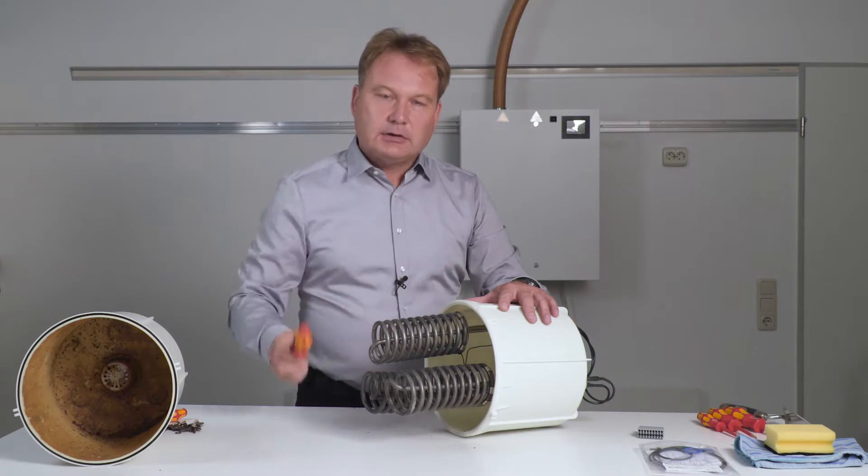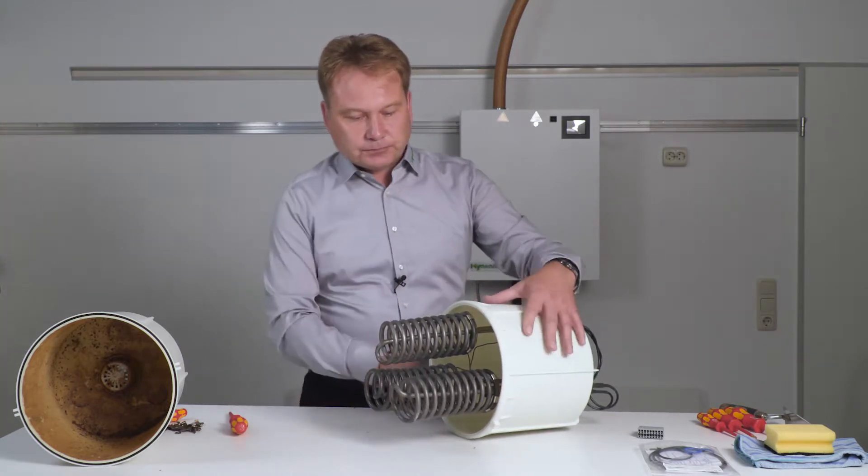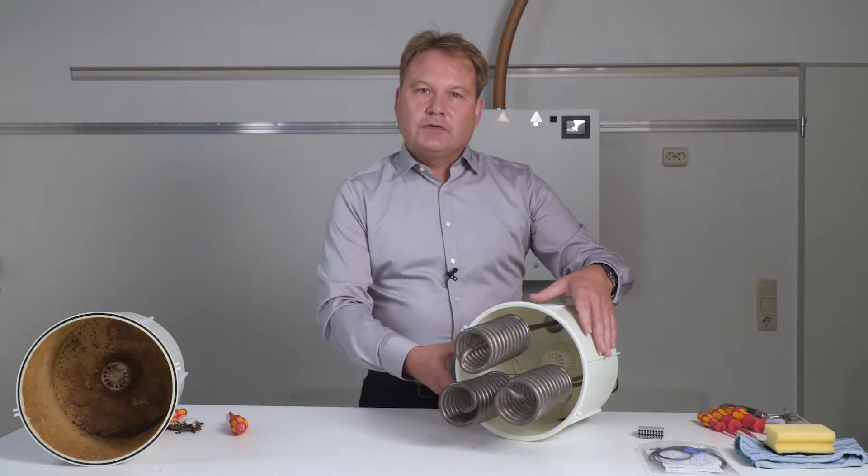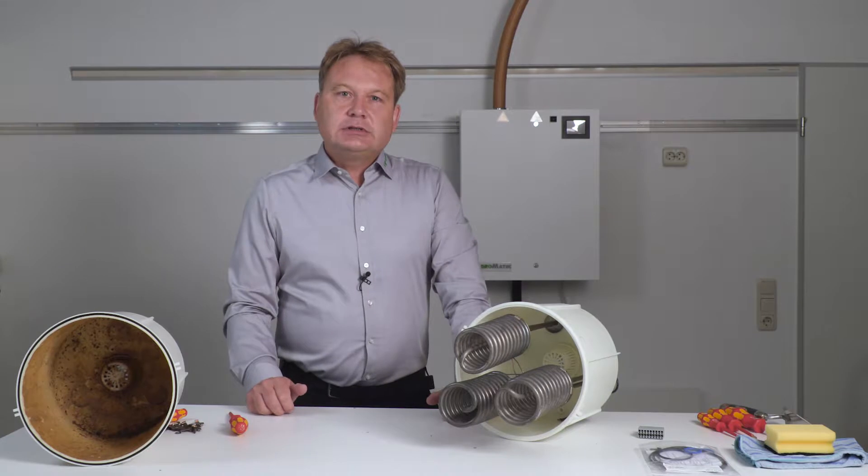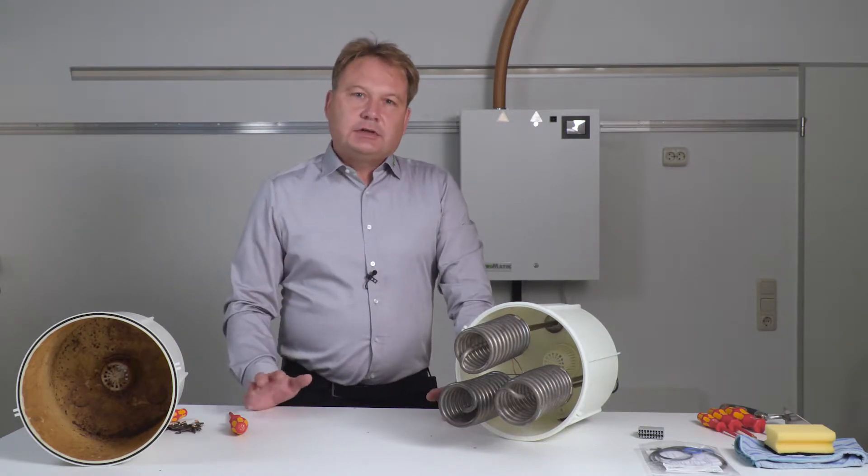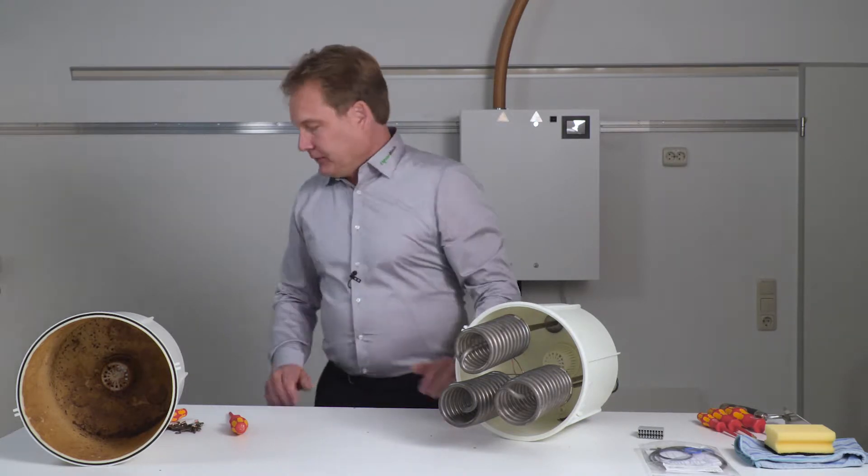Knock on the heater elements carefully so the coarse particles fall off. If the particles can't be loosened, you can use a descaling agent. Citric acid has worked quite well. Please don't use citric acid in concentrations above 10%.